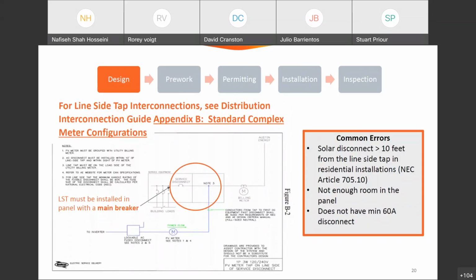So line side taps. This is a diagram here in the interconnection guide. Just note that when you do a line side tap, we do allow piercing taps within main panels on a case-by-case basis. So just because we allow line side taps in panels, please don't assume that it's a sure thing without looking behind that dead front and making sure that you have adequate space in there to make a safe tap. Because, like I said, it's definitely not a given. So when you do that tap, ideally your solar disconnect is within 10 feet or as close as practical on the outside of the building to the main service.